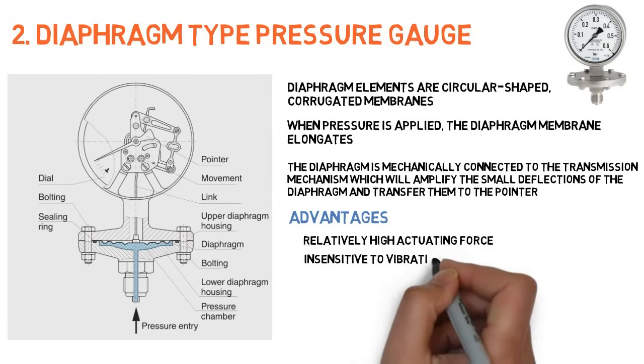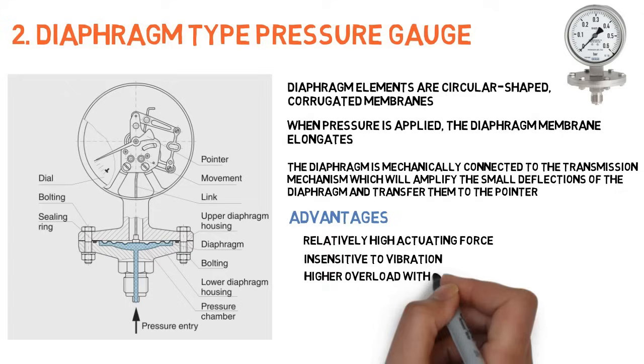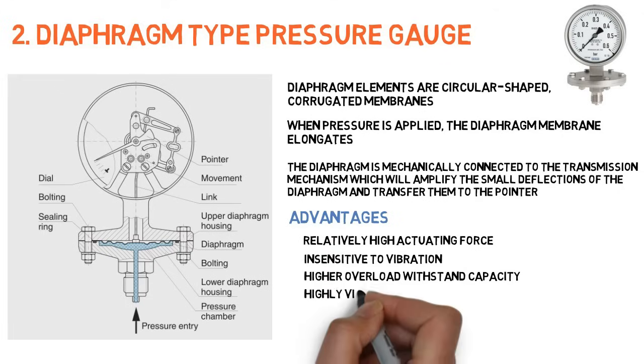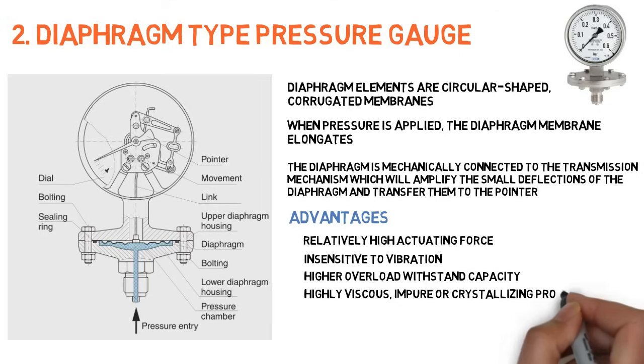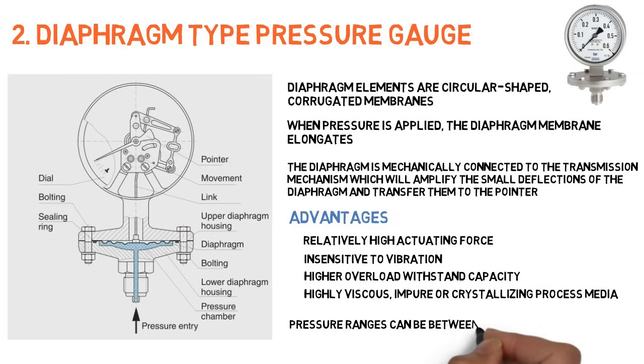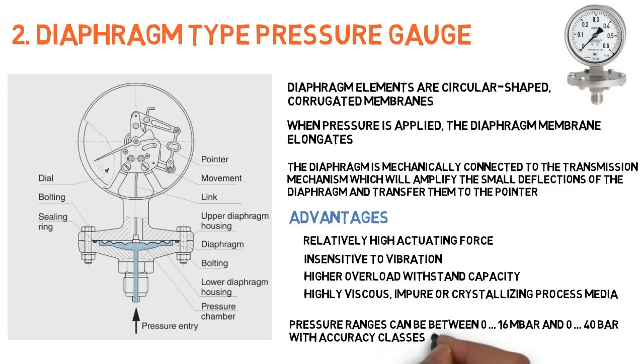The diaphragm element can be subject to higher overload. It is used for measurements with highly viscous, impure, or crystallizing process media. Pressure ranges can be between 0 to 16 millibar and 0 to 40 bar, with accuracy classes from 0.6 to 2.5.